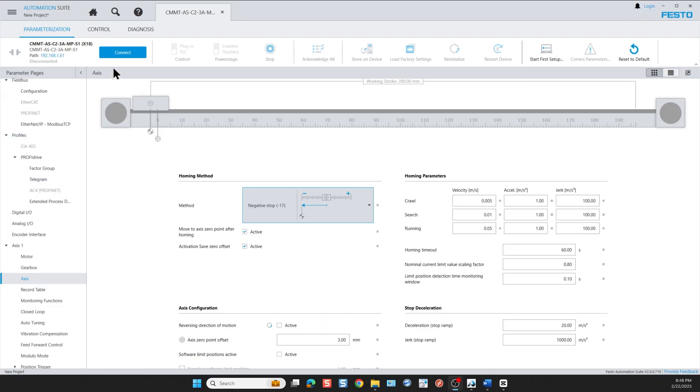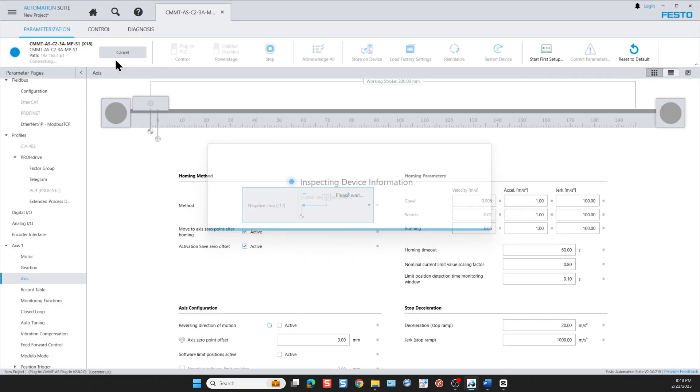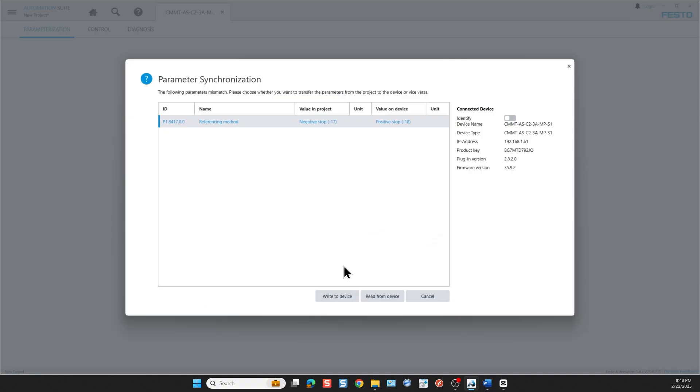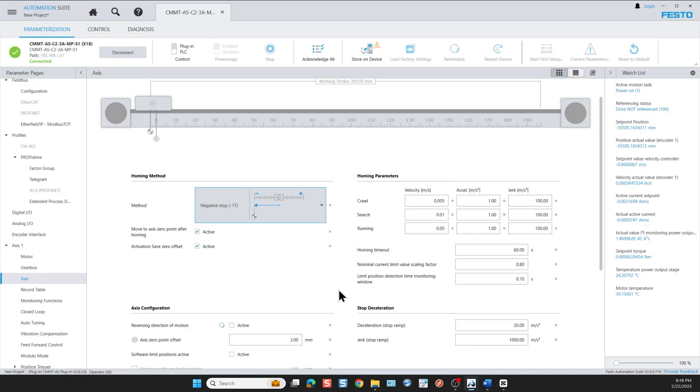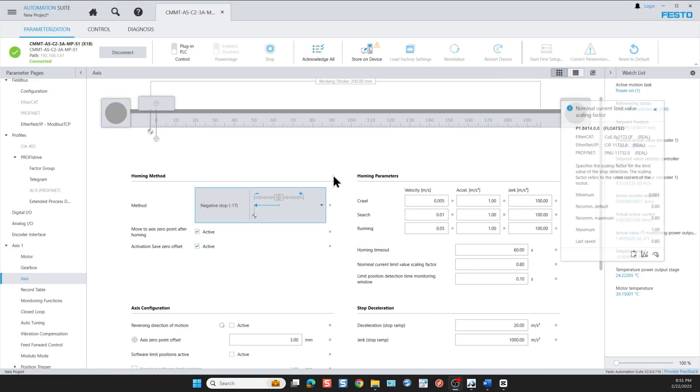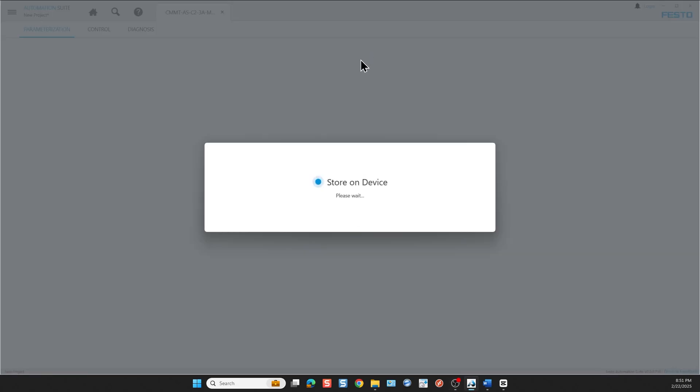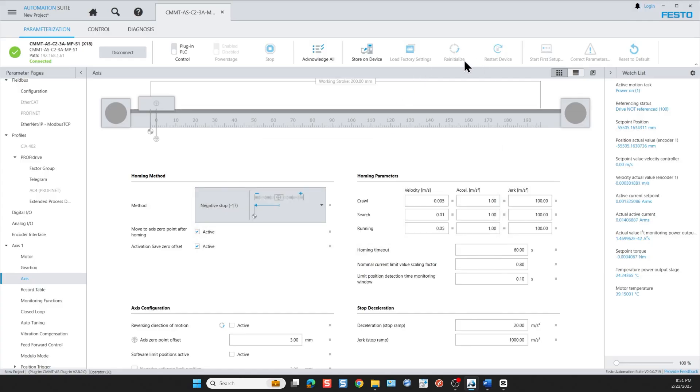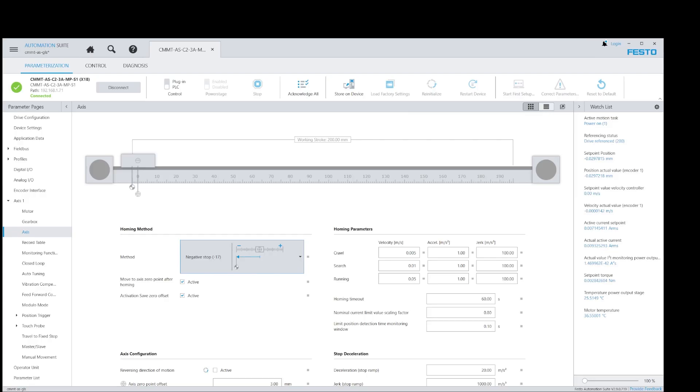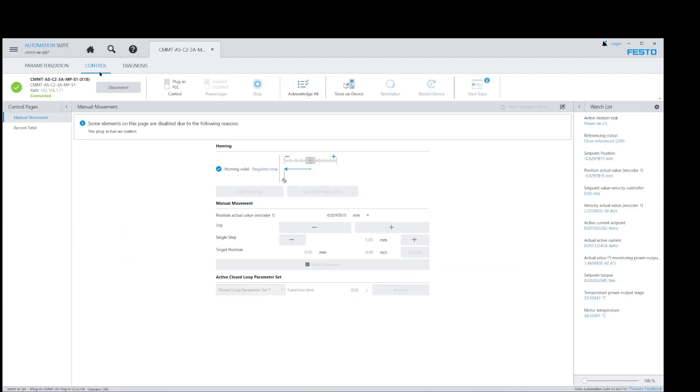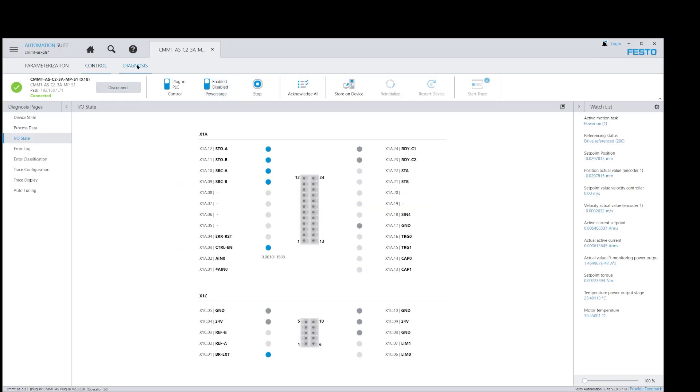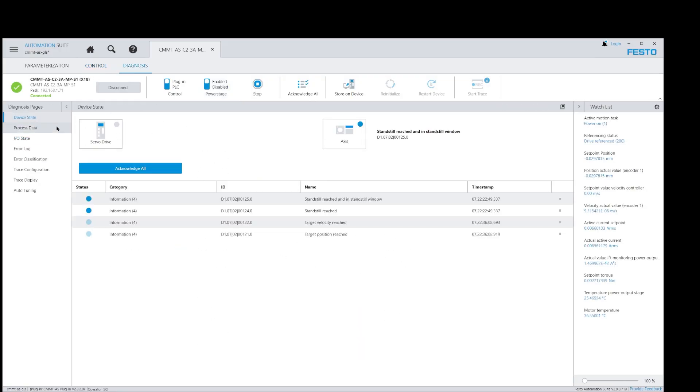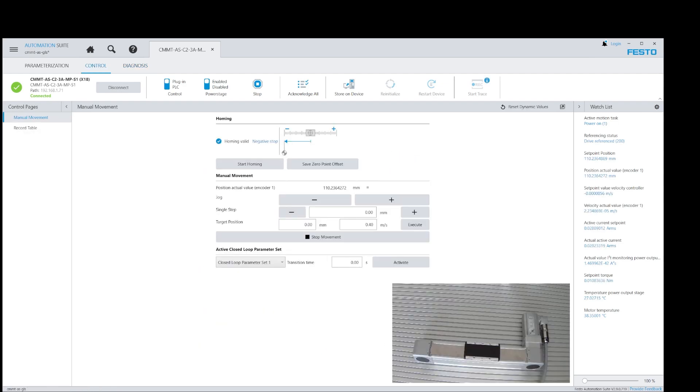At this point we want to commission the controller by itself just using the Festo Automation Suite software. I'm going to write to the device because I don't want anything that's in the device to be left. Now we're online and want to store the project on the device and re-initialize the device. Because this is a newly downloaded project you might have a few errors. I'm going to accept all so that we have a green LED on the FAS project. In order for any movement to happen by the automation suite, next step is to take control using the plugin. This is taking the control sovereignty away from anything outside this FAS software. And I want to enable the power stage, after which we go to the diagnosis to check for any errors. Then we go to IO state. I have wired the STO A and B so that there's no e-stop control enabled. Hardware signal is on, otherwise I would not be able to enable this drive. Let's start with a homing sequence.